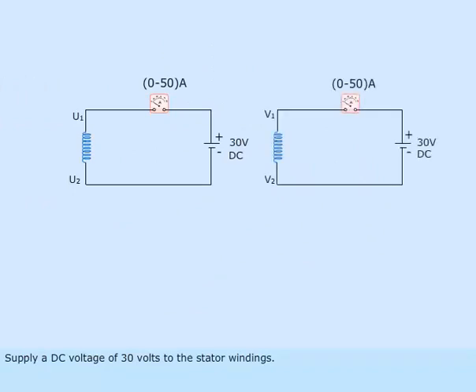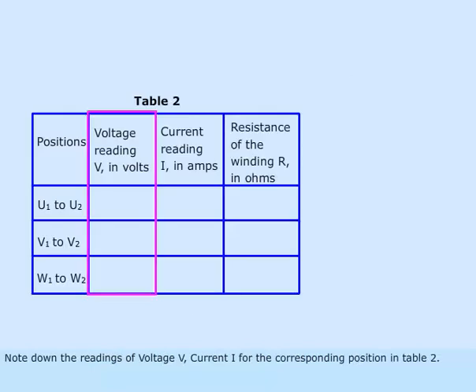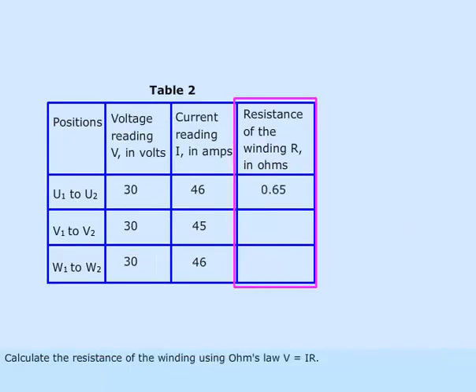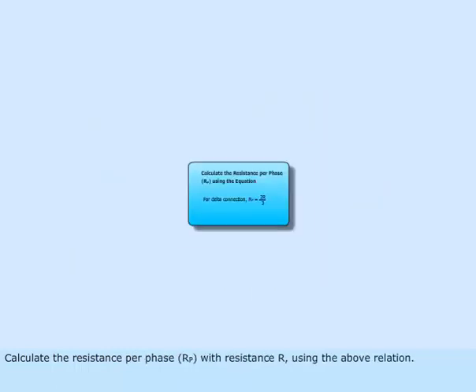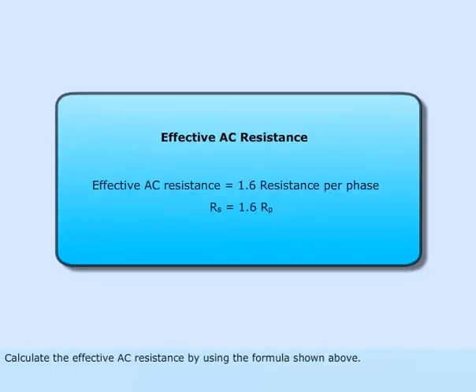Supply a DC voltage of 30 volts to the stator windings. Note down the readings of voltage V and current I for the corresponding position in table 2. Calculate the resistance of the winding using Ohm's law V = IR. Calculate the resistance per phase RP using the above relation, then calculate the effective AC resistance using the formula shown above.